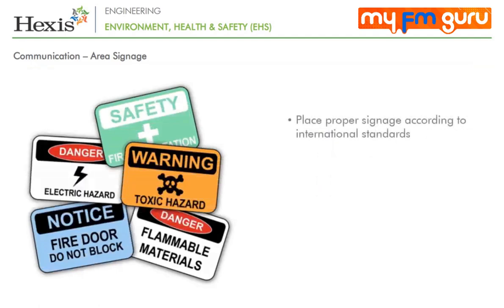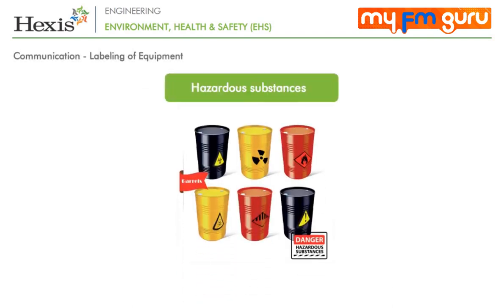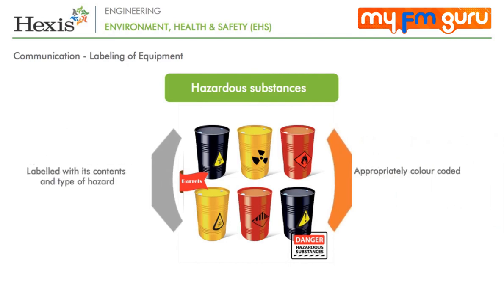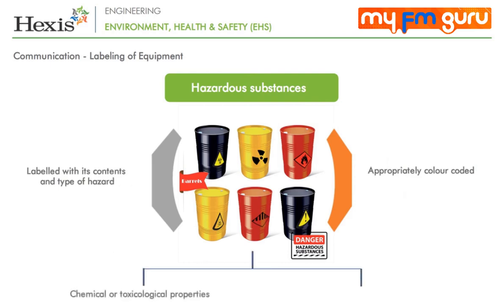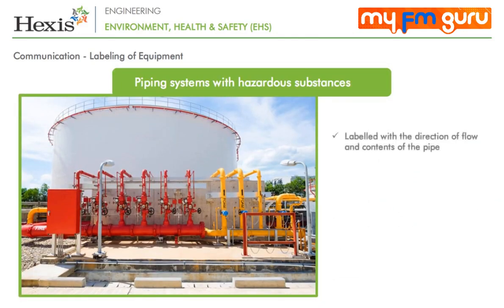Proper signage should be placed according to international standards so that workers, visitors and the general public can recognise and easily understand them. The proper labelling of any material or equipment is equally important to identify them quickly. By reading labels and using colour codes, one can know the contents, type of hazard if any, and chemical or toxicological properties including temperature or pressure of any substance. Piping systems that contain hazardous substances should be labelled with the direction of flow and contents of the pipe, and colour coded where passing through walls or floors.